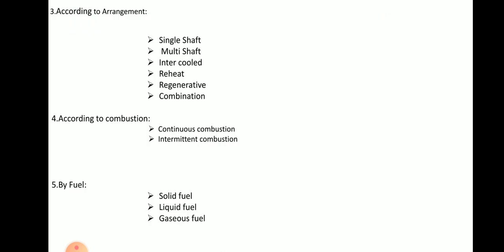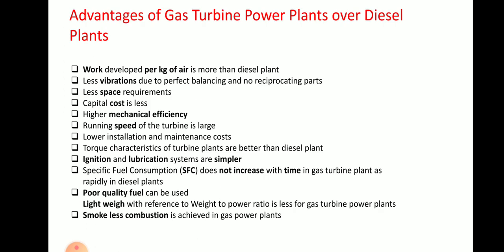Now, what are the advantages of gas turbine power plants over diesel plants? First, work developed per kg of air is more than diesel plant, so the weight of this power plant is less. Next, less vibration due to perfect balancing and no reciprocating parts, because generally it is rotational — so no reciprocation and no problem of balancing.